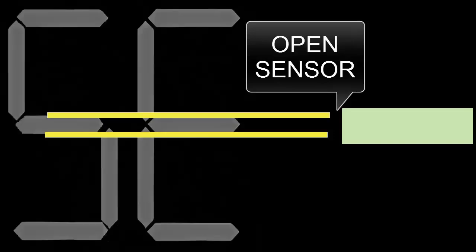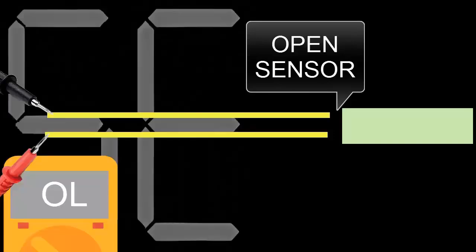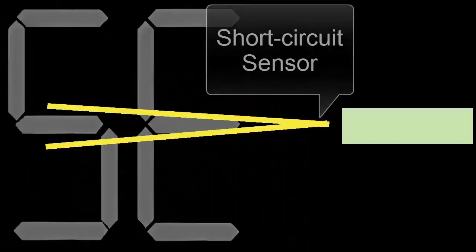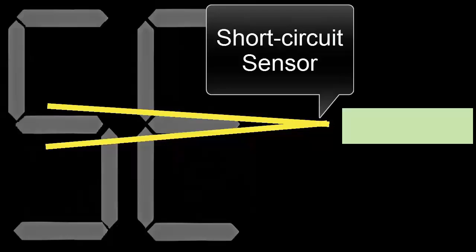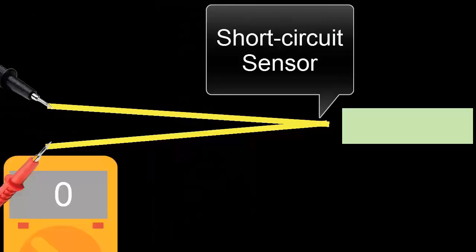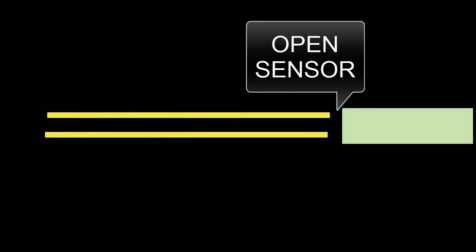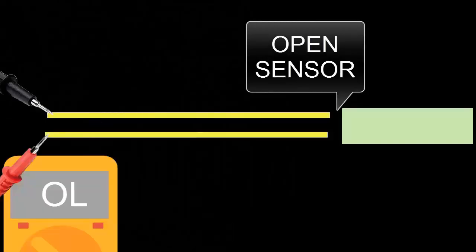C. Measurement with a multimeter. Set the multimeter to the kilo-ohm scale. D. Disconnect the defrost sensor carefully and measure its electrical resistance. A value of 0 indicates a short-circuited defrost sensor, which is the reason for the 5E error code. An infinite value indicates an open circuit, also causing the 5E error code. In both cases, the sensor is defective and must be replaced.